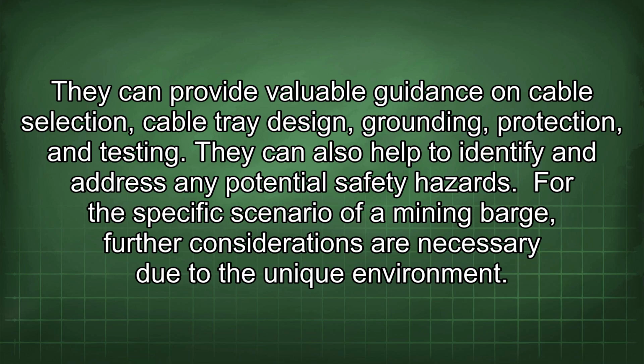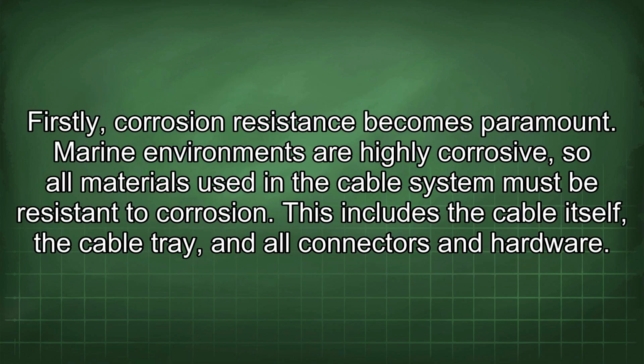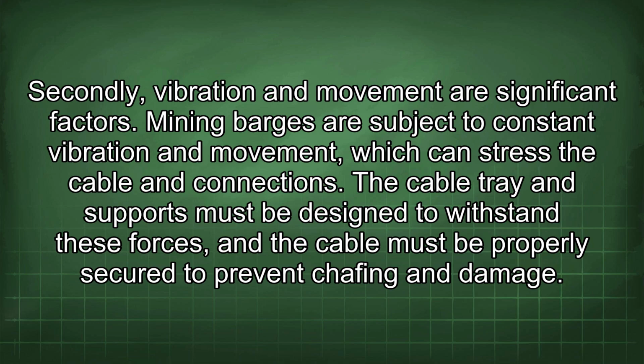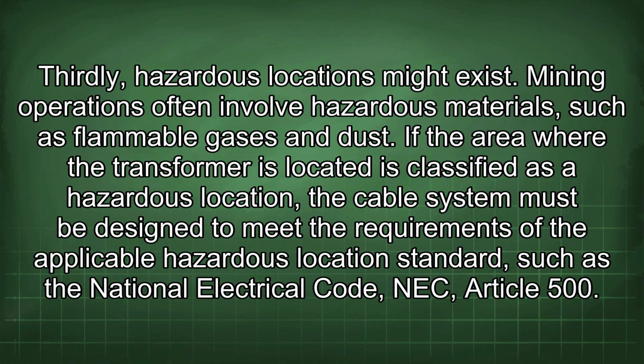For the specific scenario of a mining barge, further considerations are necessary due to the unique environment. Firstly, corrosion resistance becomes paramount. Marine environments are highly corrosive, so all materials used in the cable system must be resistant to corrosion. This includes the cable itself, the cable tray, and all connectors and hardware. Secondly, vibration and movement are significant factors. Mining barges are subject to constant vibration and movement, which can stress the cable and connections. The cable tray and supports must be designed to withstand these forces, and the cable must be properly secured to prevent chafing and damage. Thirdly, hazardous locations might exist.